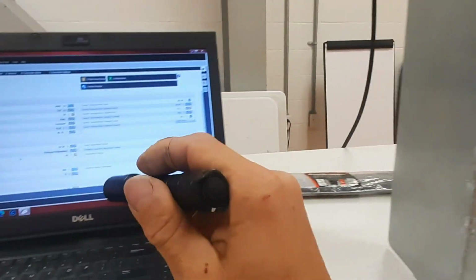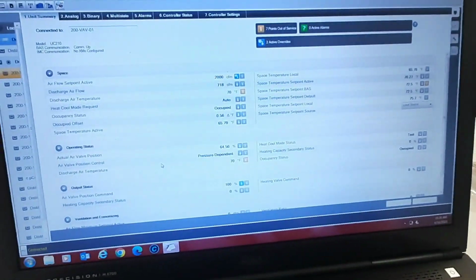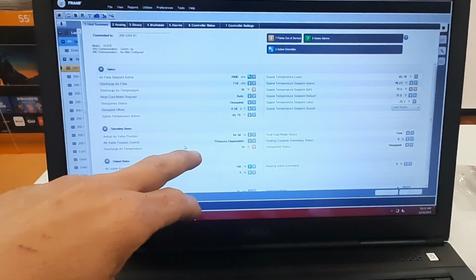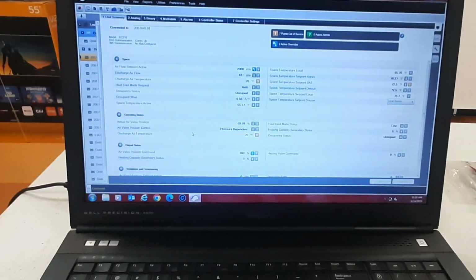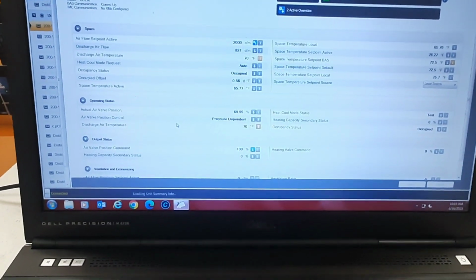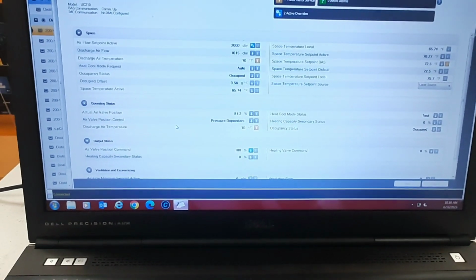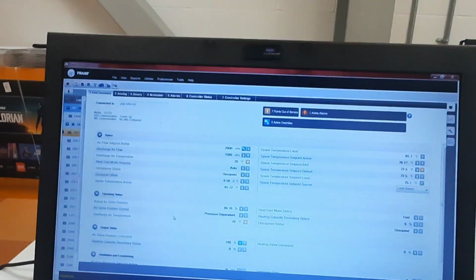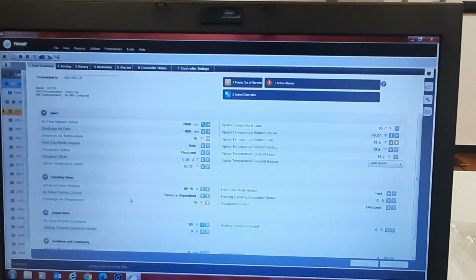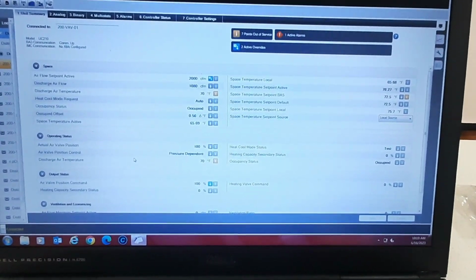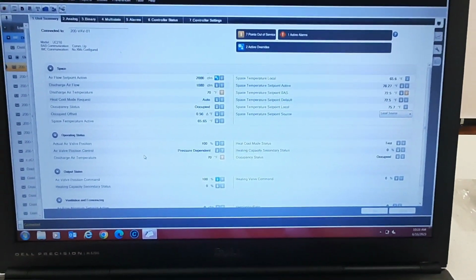My damper works. We just got some settings that are screwed up. It looks like my min max was set, but my min was set at 180. Well, I guess I was showing 120 CFM, so maybe that's why. Let's see how many CFM we get out of it at 100%. I can hear the airflow now. I can feel the airflow. It's pretty cool in here already. So it looks like I'm gonna be able to get about 1080 CFM max.